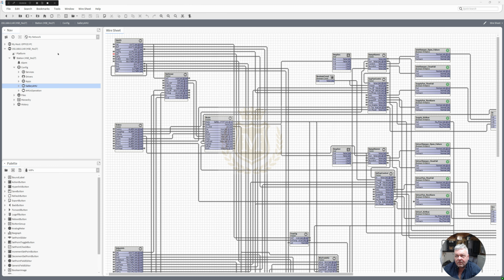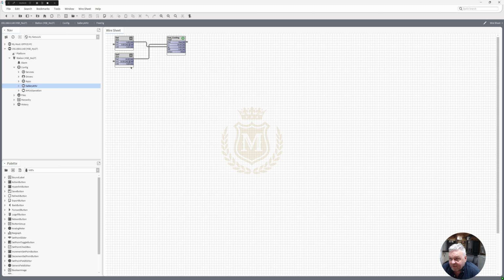So this is not connected to anything, but I've basically put the outside air at 0 here, and the external temperature coming back at 10. It's all hypothetical, but I'm trying to show you about the free cooling. So if we follow this through, this is my free cooling folder here in this logic. So external temp is 10, outside air is 0, so it's really cold outside. So free cooling is available. So outside air is 0, external is 10. So we've basically got a differential there.